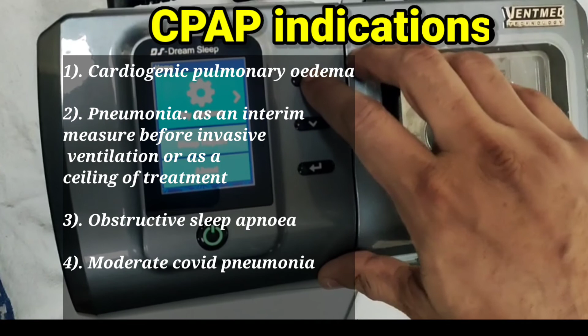So let me show you how this works. I have this VentMed BiPAP device. So the first thing that you need to do is learn the settings of every machine. Remember that the mode is ST. ST mode is the BiPAP mode, and the CPAP is written as CPAP. So we are in the ST mode here. As you can see, the IPAP is 14 and the EPAP is 8. IPAP is the inspiratory pressure that we have to give, and EPAP is the expiratory pressure.